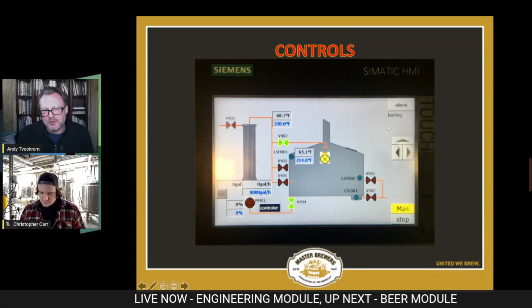And that's kind of a safety feature. You can set that, which is currently set there at 214 degrees. If you set that and for some reason the kettle gets over that temperature, it would shut off the steam, and might shut off the pump as well. But in our situation, usually we just set that right there at 214, and it never quite gets there, which is fine because we're really regulating the temperature coming out of the EWB. So it's set at 220. You can put that anywhere you want, but what we found is when you're running at 220, it'll get to that temperature, and then the steam will shut off. It'll run for a while till it cools back down, and then the steam will open back up.